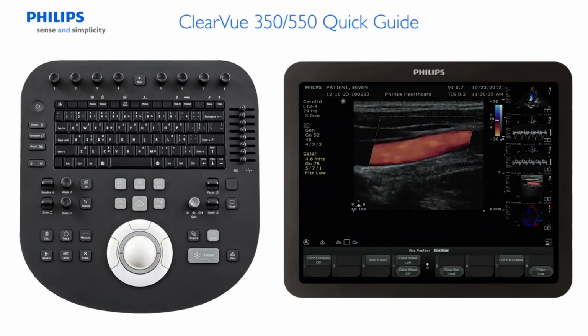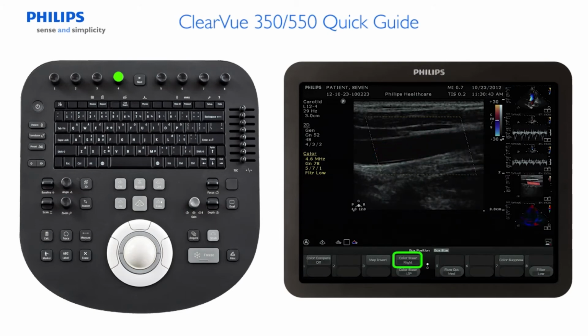When using a linear transducer for color imaging, pressing the Color Steer Quick Key allows color box steering to preset angles such as left, center, and right. Rotating the Color Steer Quick Key allows for incremental steering angles. Optimize the image by using iScan.